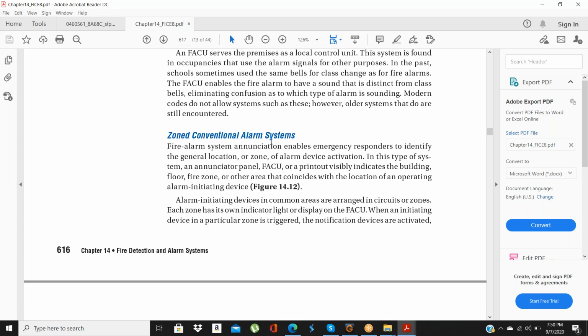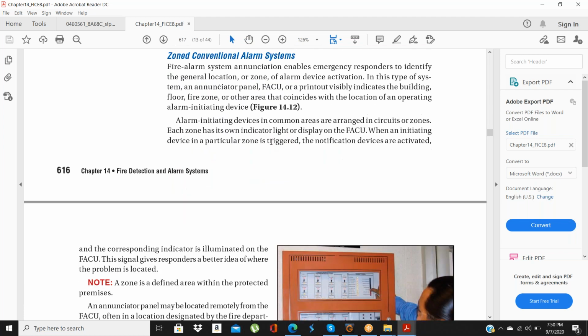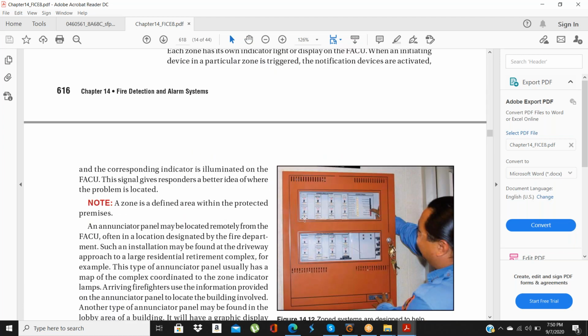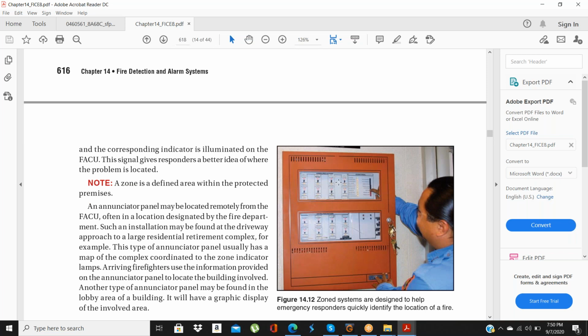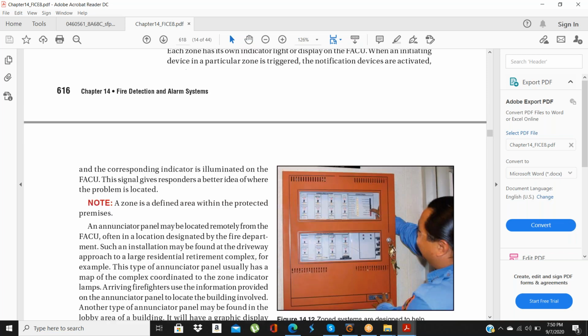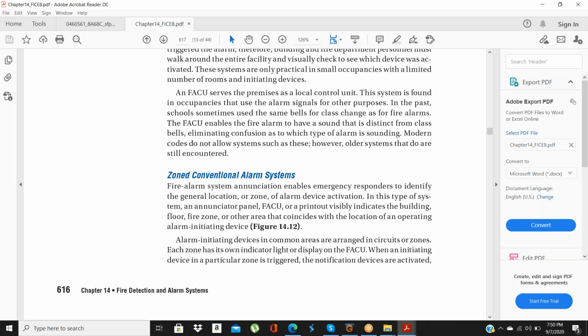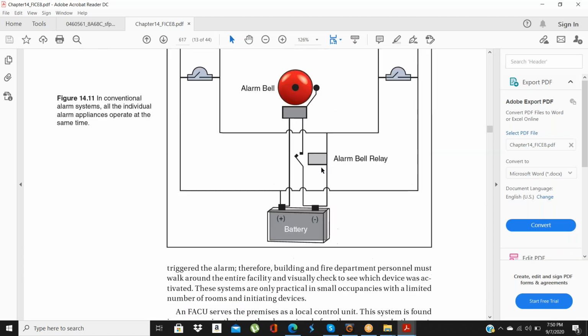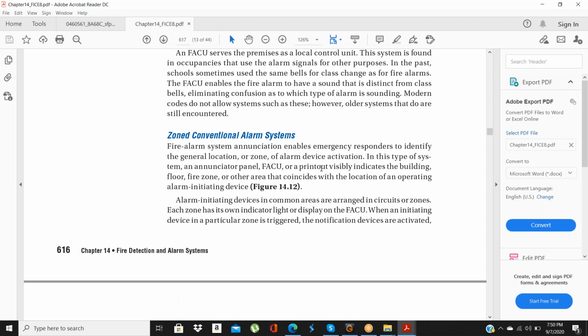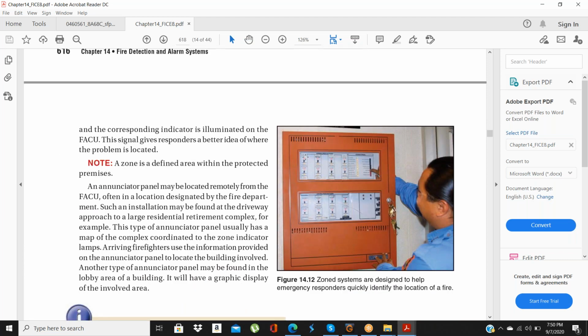Zone conventional alarm systems are installed in separate zones. The control panel will show zone 1, zone 2, zone 3. This is a bit more engineered than the simple one. If there is a problem in zone 1, it will detect only zone 1; if there is a problem in zone 2, it will activate that zone. Once the operator reaches, he will see where the problem is and go directly there to solve it.